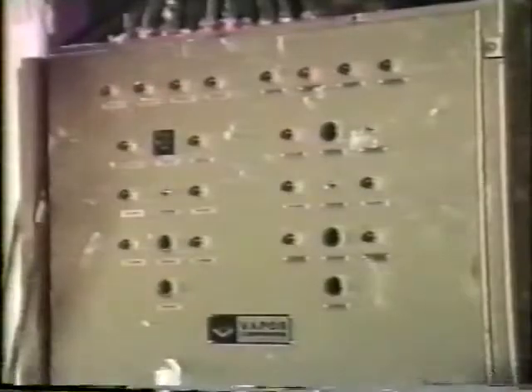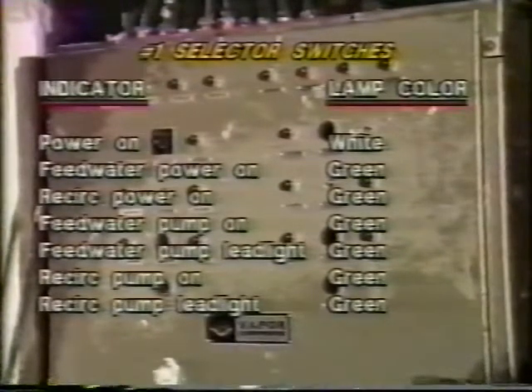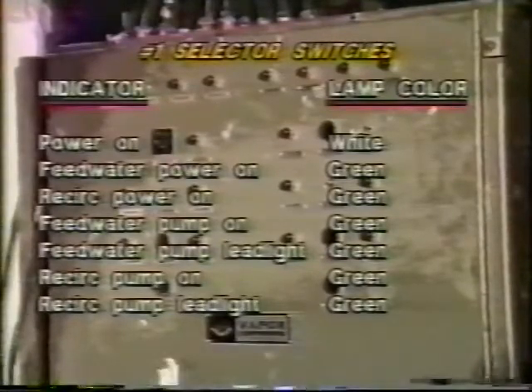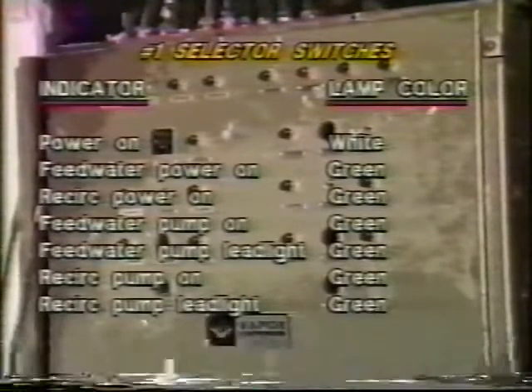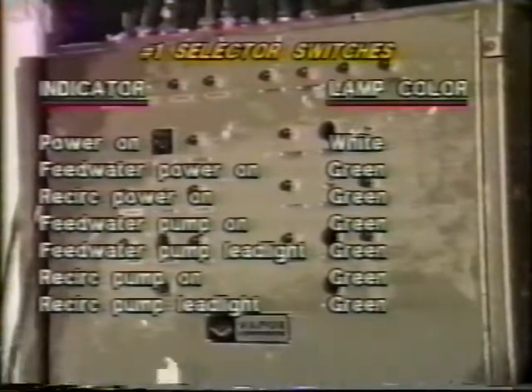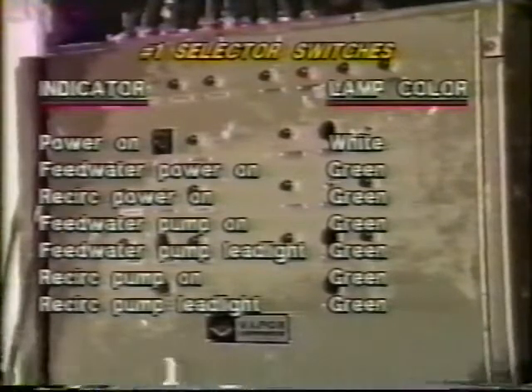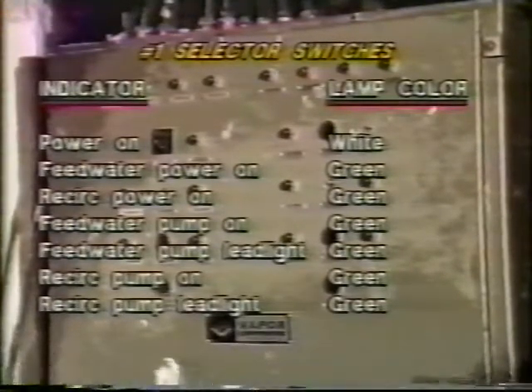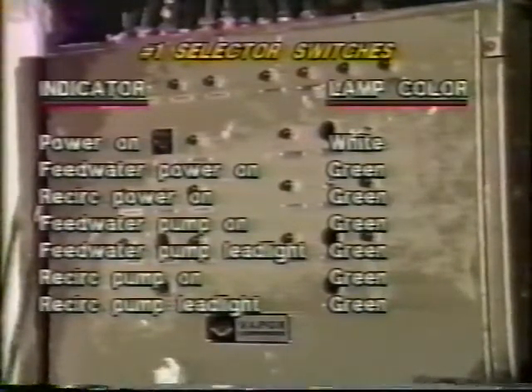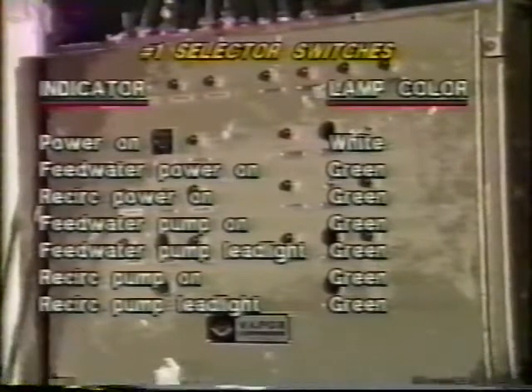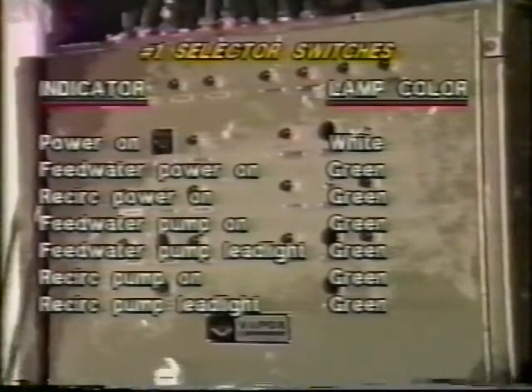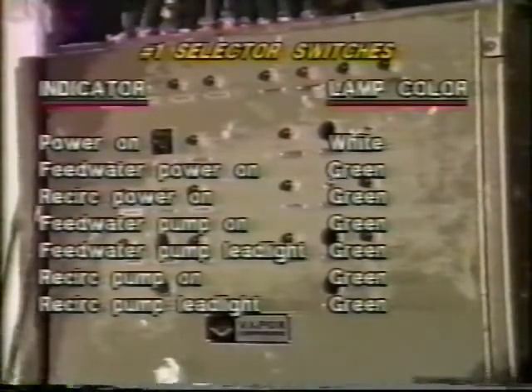If the number 1 position is chosen for all selector switches, the following white or green lights should be lit. The white power on light. The green feed water power on light. The green recirc power on light. The green feed water pump on light. The green feed water pump lead light. The green recirc pump on light. And the green recirc pump lead light. When these indicators are all lit, the system pressure controller is set to the required pressure.